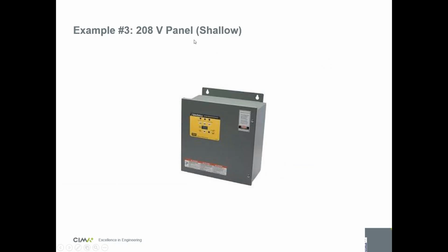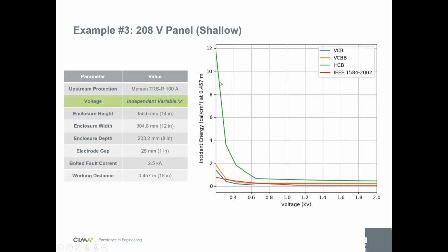So third example, let's say we have a shallow panel this time. What's the impact? We're going to see the impact of the depth on this one. So the 208 volt panel. If we plot the voltage, there's no 2-second rule this time. It's protected by a Mersen TRS-R 100 amp fuse. So let's say we have a voltage here. You see the HCB is always the highest.